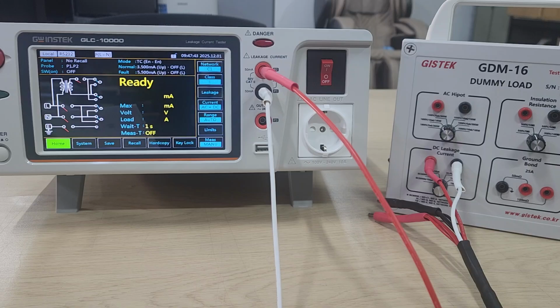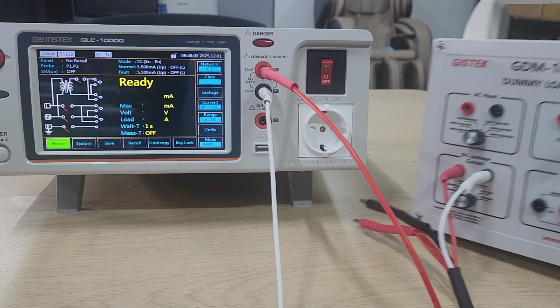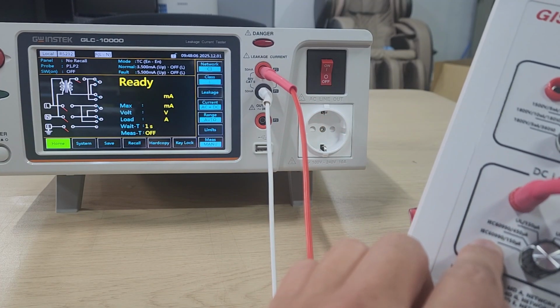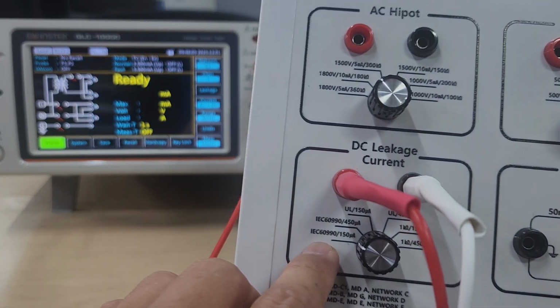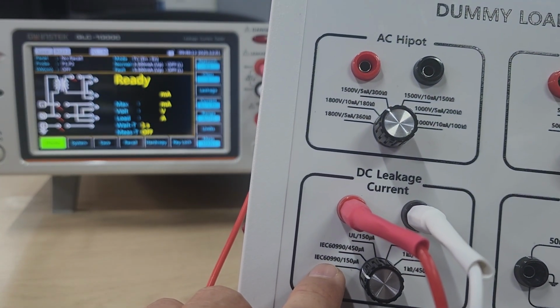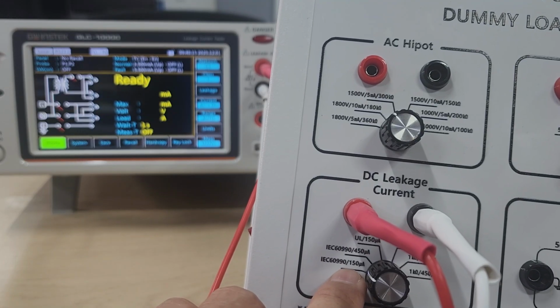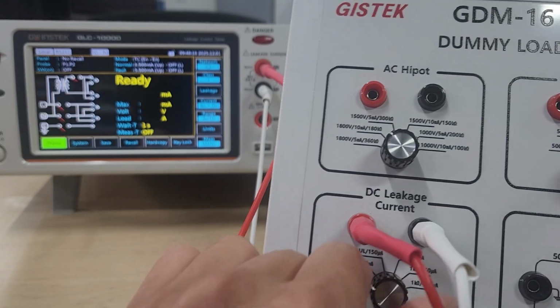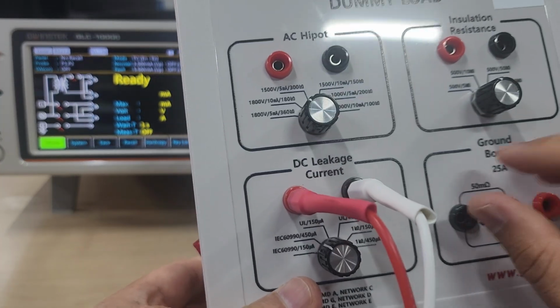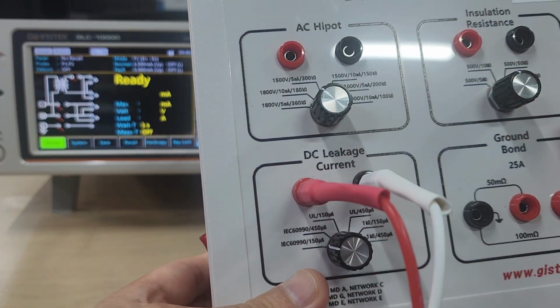Select the DC leakage current test channel from the dummy load. For example, turn the knob to select the IEC 60990 standard 150 microampere channel. IEC 60990, 150 microampere. Turn the knob. White cursor.